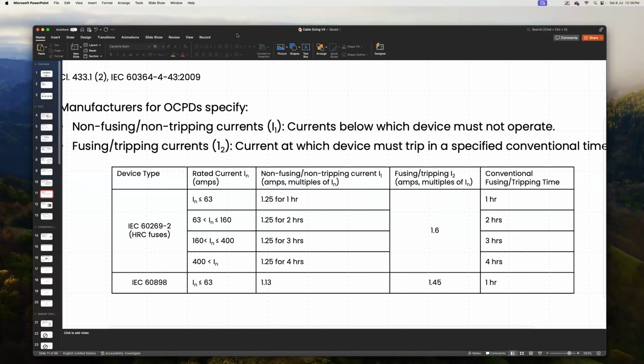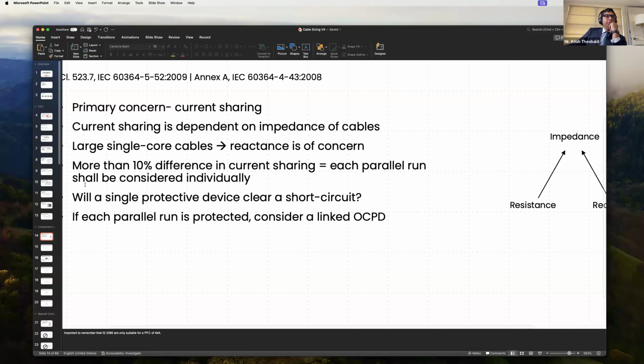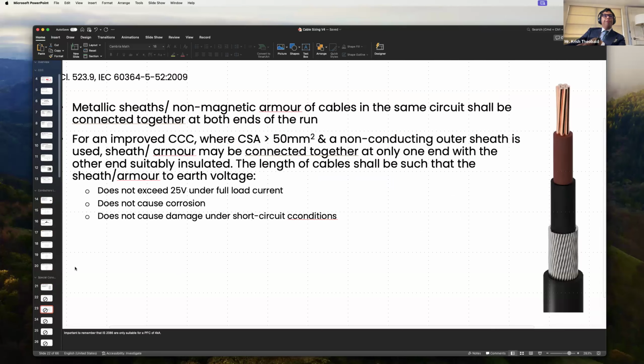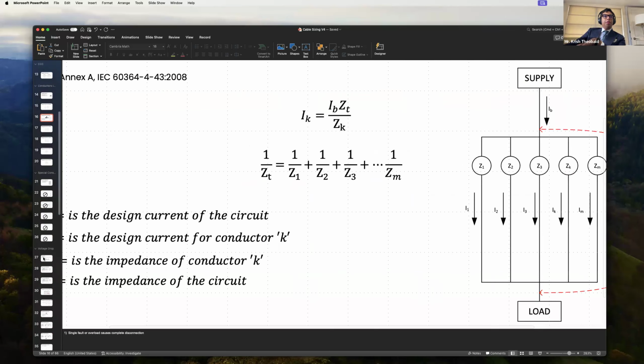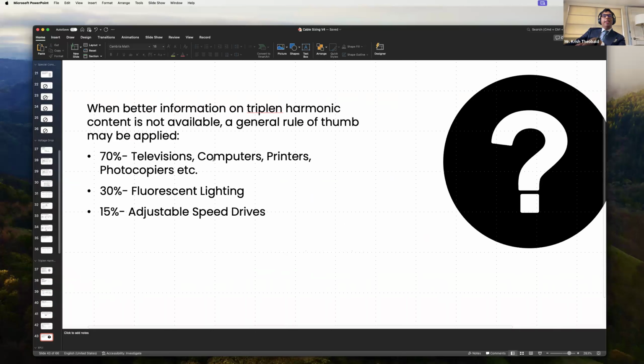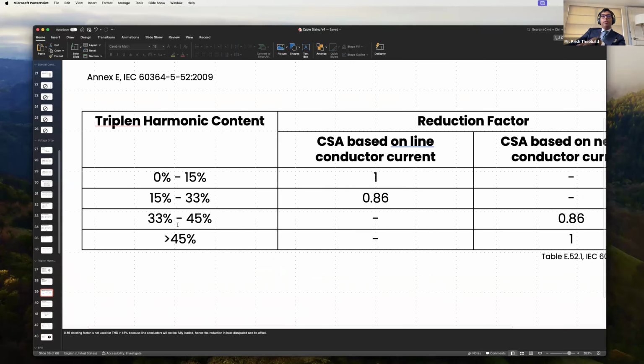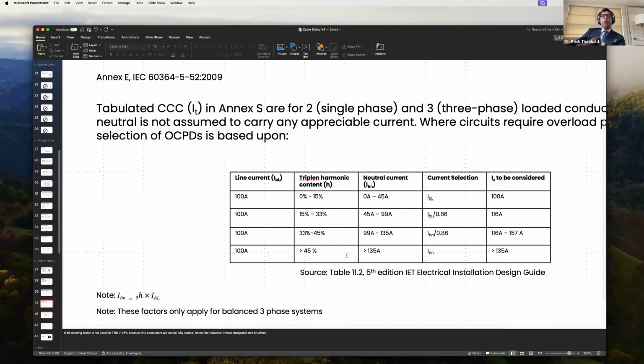Why is the neutral conductor double the size of the live conductor in data centers and other IT installations? Interesting question. If you have IT equipment, you can have almost 70% total harmonic distortion. We even saw one light bulb had 120. If we use this to calculate, 70 times 3 is 210. So twice the current is flowing in the neutral conductor as in a line conductor. That answers your question.